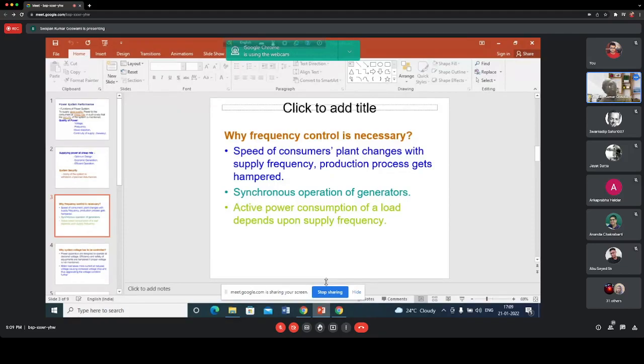Now assume the frequency of the system is increased. The speed of the induction motor will also increase, but the load is constant, so the motor is now transporting the same load at a higher speed, and the power consumption will increase. So with an increase in supply frequency, power consumption by the load will increase, and similarly, with a reduction in supply frequency, power consumption by the load will decrease.